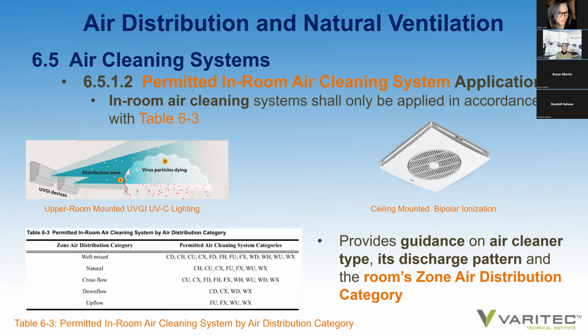With that in mind, we can now look at what system might be permitted in which application. If you look at a well-mixed zone, you can see that ceiling downward flow air cleaning solutions are viable. Ceiling horizontal throw air cleaning systems are capable. For a downflow system, only ceiling downflow, not ceiling horizontal. For upflow systems such as UFAD, we look at floor and upflow, et cetera. So this table 6-3 gives you an understanding of, depending on the technology that might be applied to clean the zone of infections, that it be appropriately assigned based on this table's guidance.